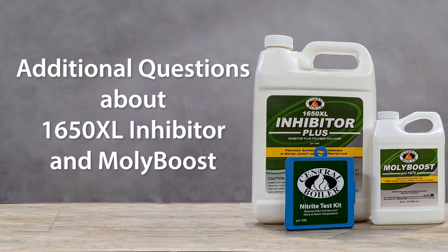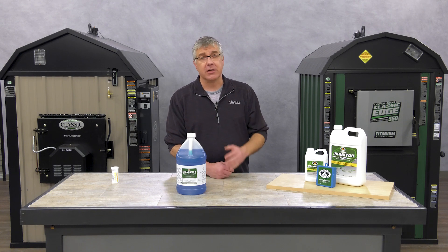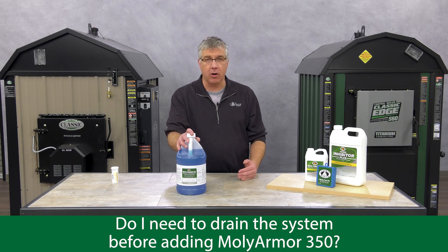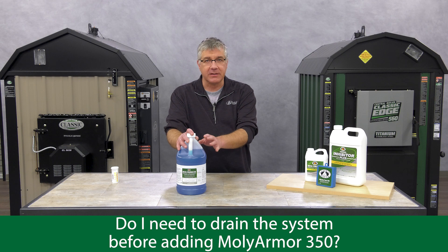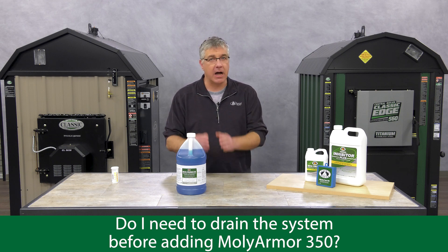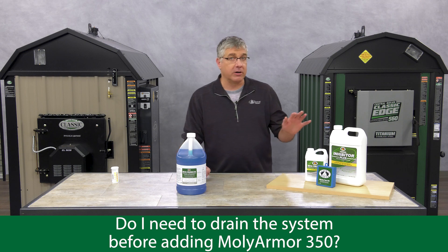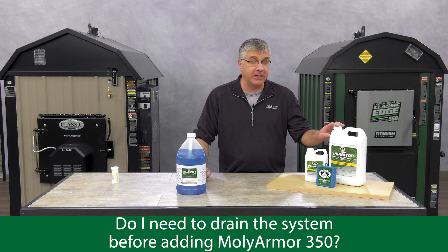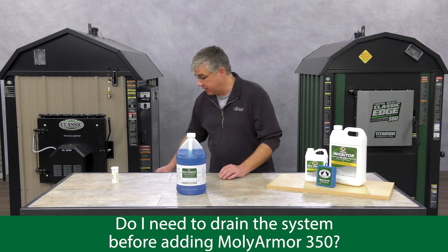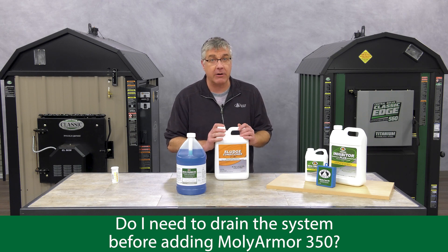This is an addendum for those of you who have used 1650 XL corrosion inhibitor plus in the past. Do you need to drain the system before adding in MolyArmor 350? No. There is no problem mixing in MolyArmor 350 on top of the corrosion inhibitor plus. However, if your water is discolored orange or brown and/or your corrosion inhibitor parts per million is below 1500, there's likely some corrosion going on in the water jacket and it is best to drain the system. Get a jug of sludge conditioner and follow the directions in your owner's manual on how to flush it correctly.